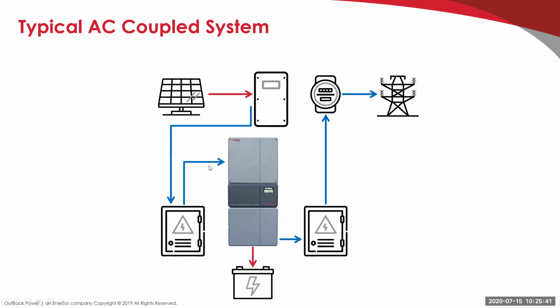So when we go to an AC coupled system, basically we're putting the inverter in series with the grid dependent inverter. So we have the DC coming in, have the DC to DC converter, and then we have the DC to AC inverter inside. So we have AC power coming out, right? And that goes into our inverter. And when we're grid connected, we have a transfer relay inside that closes between the output, this is the output, and the input. So we're just like a piece of copper wire.